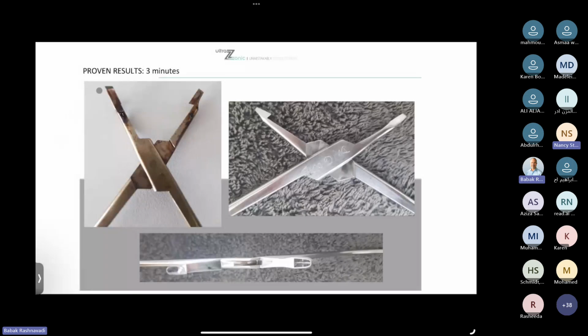Here you can see it more precisely. We have one very dirty instrument, and on the right side you see that all the dirt is gone. Even from above you see a little bit of corrosion, but all the rest, the cavities of this instrument, everything is gone. It's really so clean in 3 minutes. And if we always consider having that kind of cleaning efficacy, and you then put it in the washer disinfector to disinfect your instruments, of course you can understand your disinfection cycle is way better than what you have today when you just clean your instrument in a sink. Next, please.